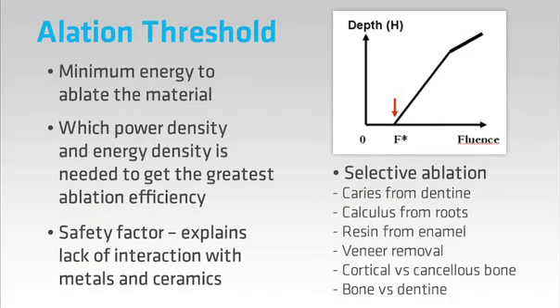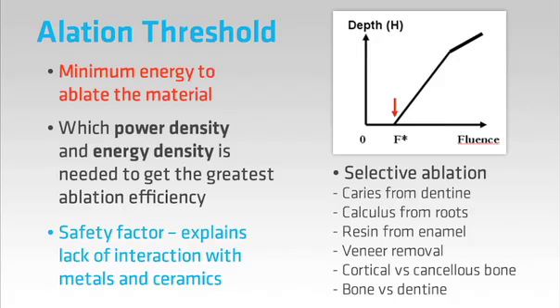A key concept in understanding how the laser works is ablation threshold. This is the minimum amount of energy delivered into a given area that we need to ablate the target. We express this in terms of intensity — that is power density as well as energy density. If we are above this threshold, the target will be cut. If we are below the threshold, the material will not cut; instead it will warm up. We can use this warming effect of low intensities to great benefit, to coagulate and thereby to control bleeding.